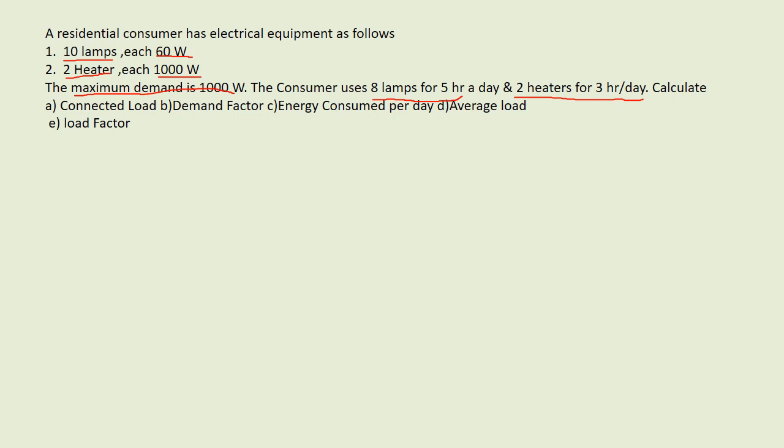Okay, so this is the way he uses the things. We need to calculate the connected load, the demand factor, the energy consumed per day, the average load and the load factor. First we will be calculating the connected loads. Here, as you can see, 10 lamps and 2 heaters are the load, and each has a rating of 60 watt and 1000 watt. So your connected load will be the total load in watt.